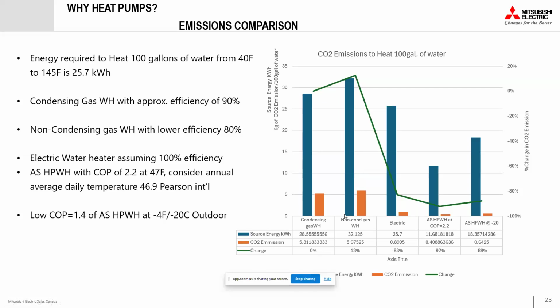Especially for the GTA area, the average annual temperature is like 47, 48. At that temperature, the COP will range 2 or 2.2, and you will consume less than half the energy. So, as you can see, for 25 from electric, I'm using 12 kilowatts of energy for the same amount of water produced.